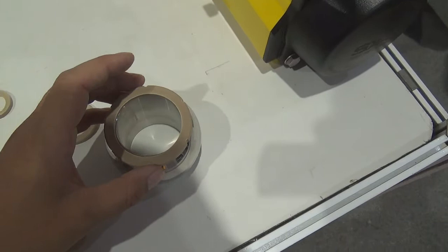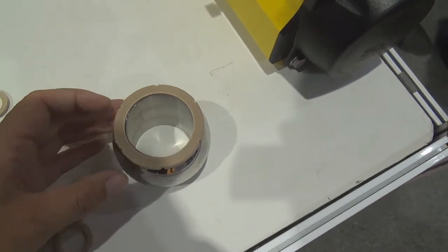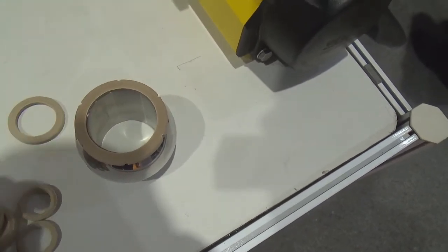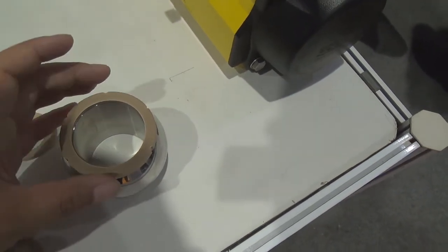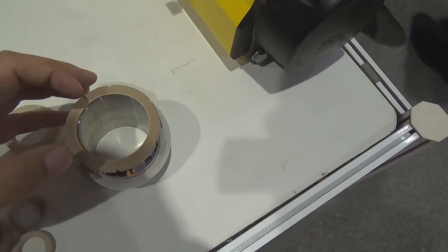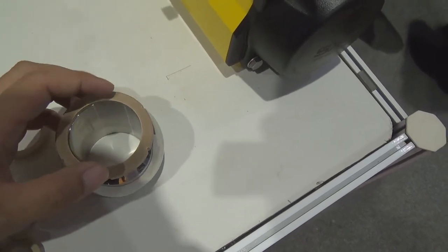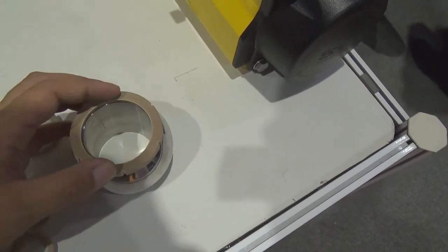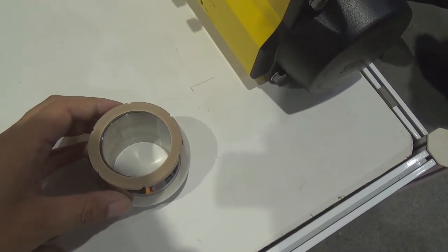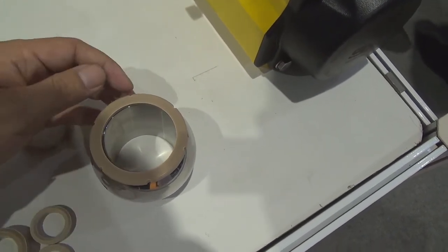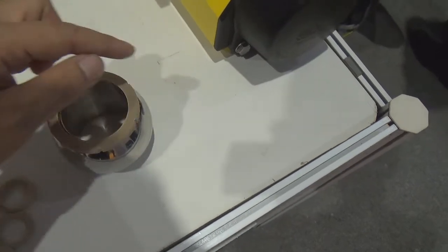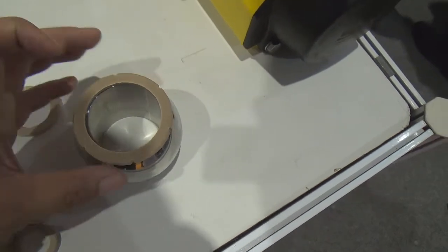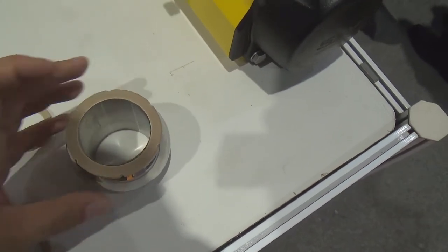When we use this kind of soft seat ball valve, the reason why we produce several grooves on the outside of the valve seat, I already talked about before. When we use this kind of valve seat, if the pressure flows to the back of the valve seat, the pressure will push the valve seat against the ball. If the valve is closed for a very long time, the valve seat will have permanent deformation. So that is the reason why we cut several grooves on the outside of the valve seat. So the pressure will flow to the cavity to relieve the pressure. So the valve seat will be safe.